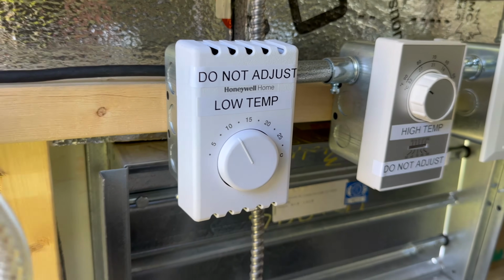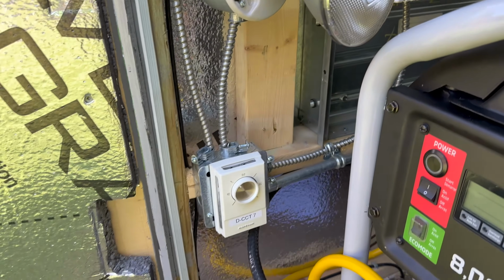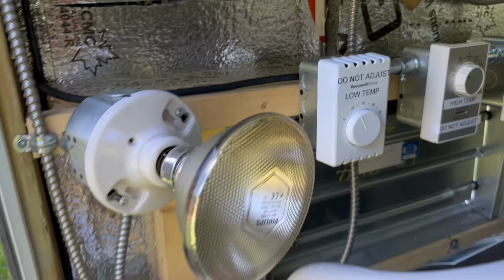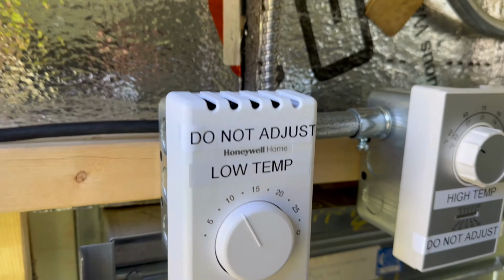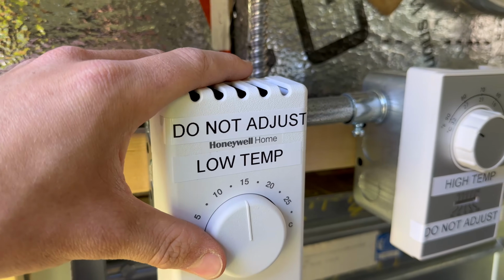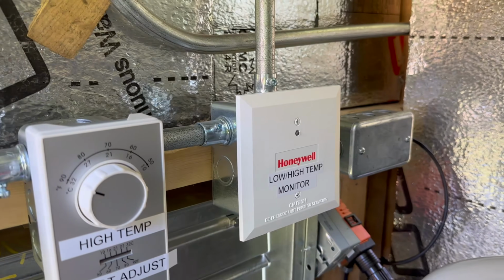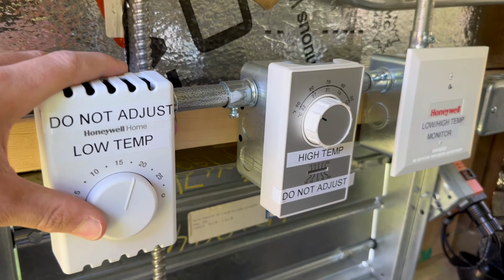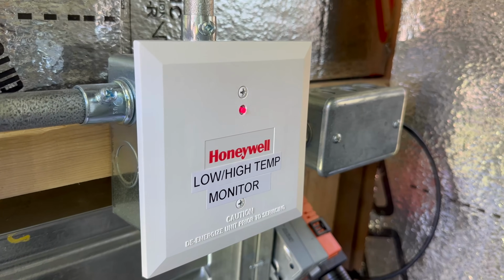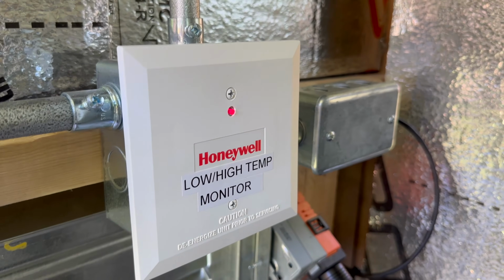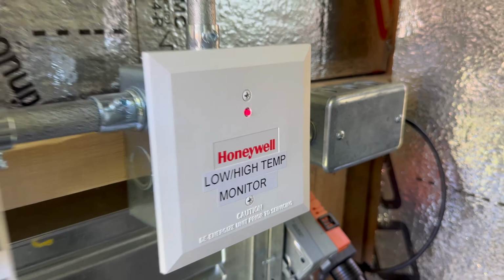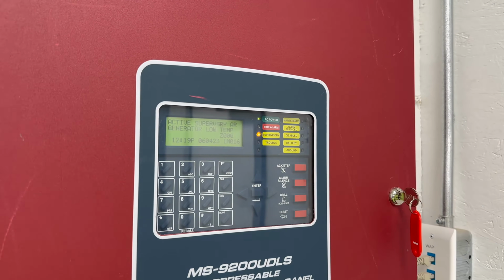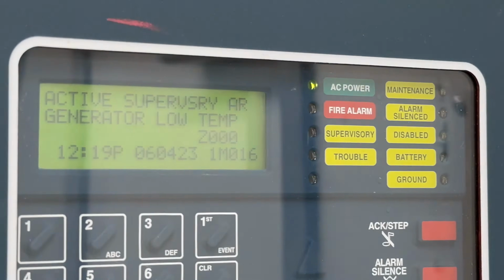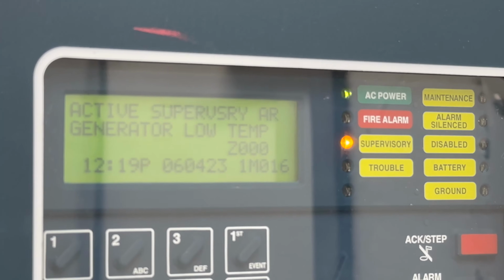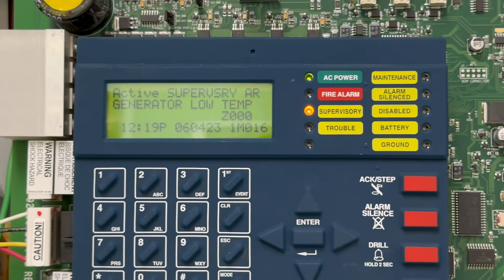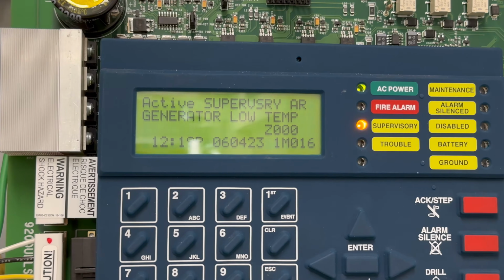For example, if for some reason our light bulb burns out or our heating system fails, the low temperature alarm will come on, which we can turn up what's considered low temperature to 25 degrees or so, and you will see that module will activate. There you can see the module has now activated and recognizes that the circuit has closed. And that gave us what is known as a supervisory at the main panel. We can acknowledge that, and this would do the same thing for high temperature.